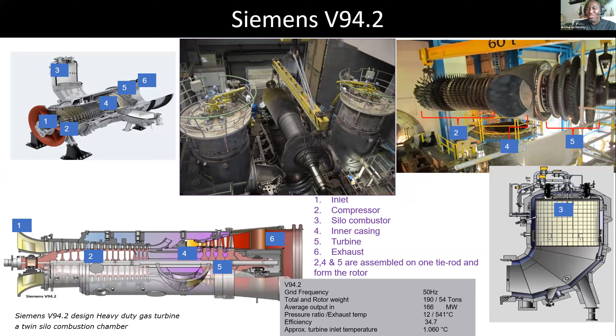Whereas for the Siemens, wow, my time is almost up, so I will be a bit fast. For the Siemens, you can do the maintenance and dismantle all of the stages because just one tie rod is holding it. In GE, it's like 6 tie rods holding all the stages together.